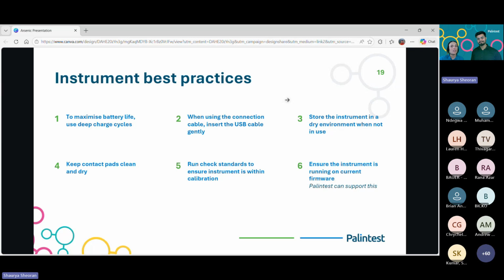Running the check standards to ensure the instrument is in calibration, and also ensuring the instrument is current on the latest firmware. Now, where you would find the firmware for every instrument is in the download section of the Palintest website. And where you would find what the instrument is currently running on is in the settings menu inside the device.